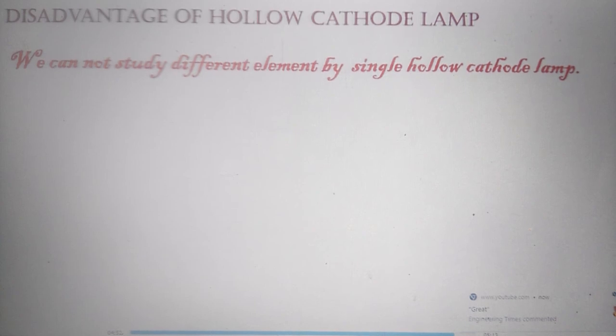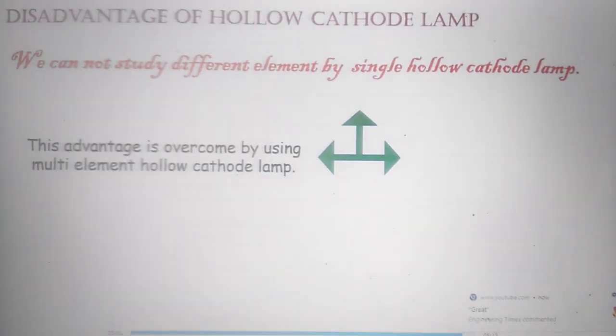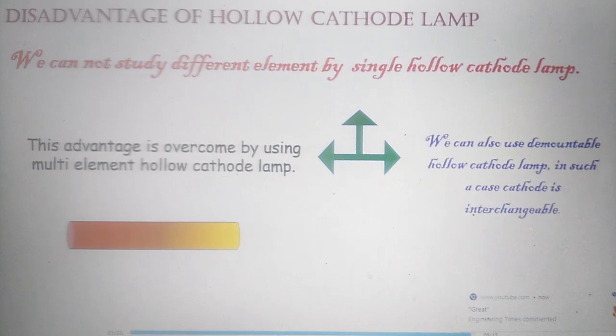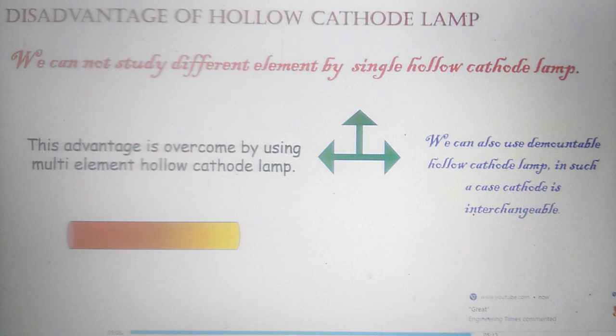A disadvantage of the hollow cathode lamp is that we cannot study different elements using a single hollow cathode lamp. This disadvantage is overcome by the multi-element hollow cathode lamp, in which the cathode consists of more than two elements. We can also use a demountable hollow cathode lamp, in which the cathode is interchangeable.